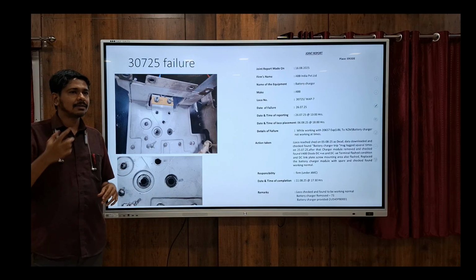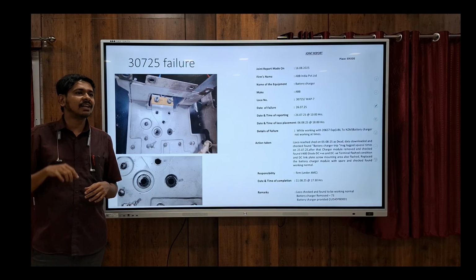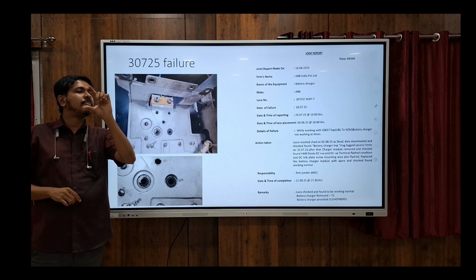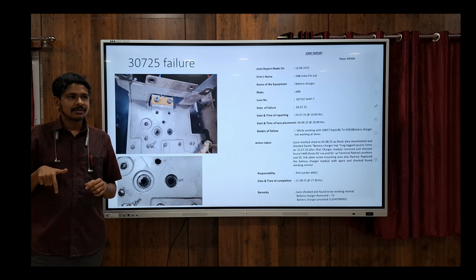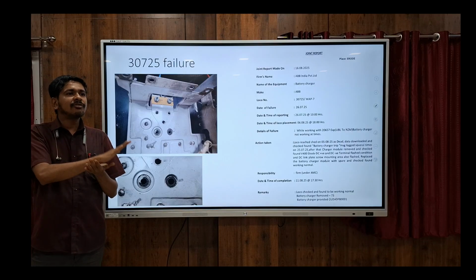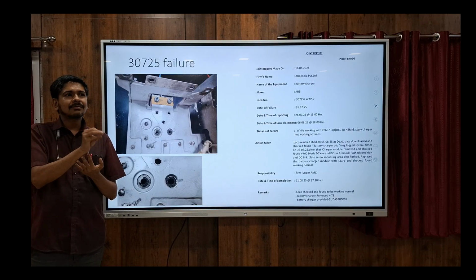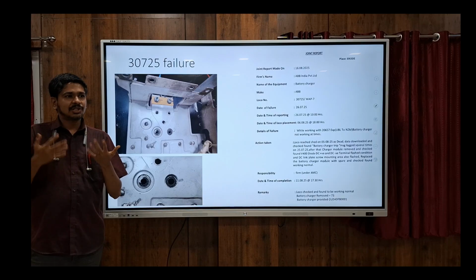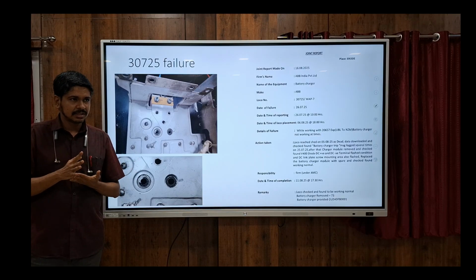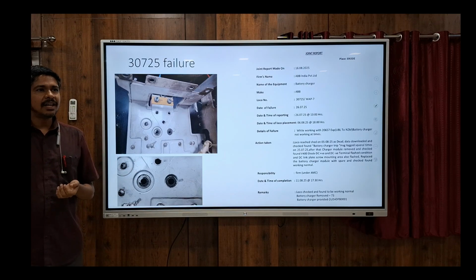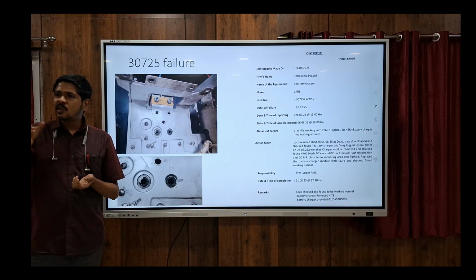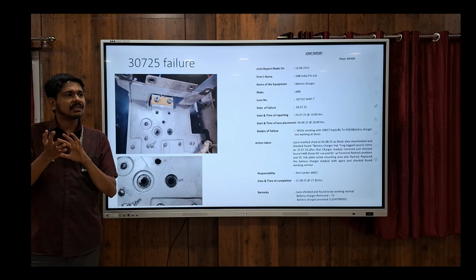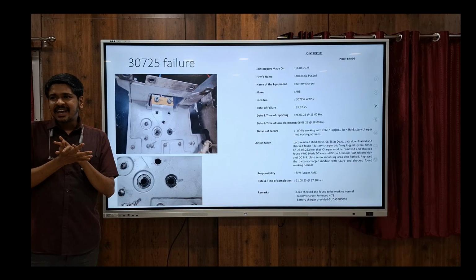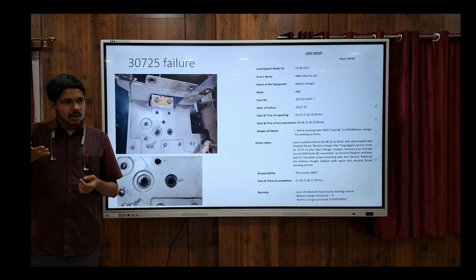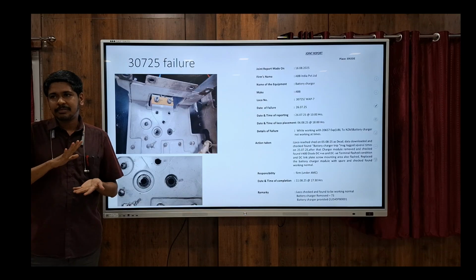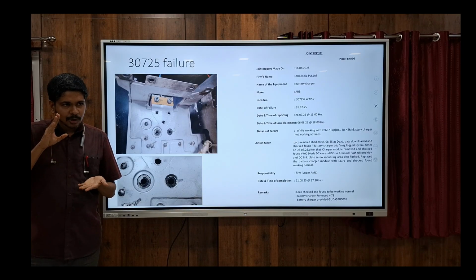One more thing is the bleeder resistor I showed, across the DC link capacitor. Why is it there? Because after turning off the loco, within a few minutes, the full charge stored in the DC link should be discharged. That is also monitored by the controller card. If that voltage is not discharged, or if that resistor has some problem, then firing will not happen and the DC link will not be built up. In such cases, the battery charger will not work.